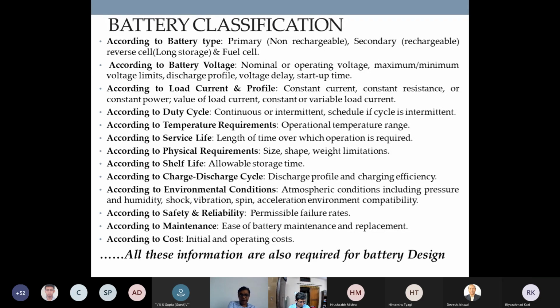Now there is another very important thing, which is temperature. What is the operating temperature range? For a battery like lead acid, the life capacity derating will be twice if I raise the temperature from say 25-degree nominal by 8 degrees. So what is the temperature - high temperature application, low temperature application? The electrolyte in a lead acid battery starts freezing at minus 16 degrees. There is IEC 60896 21 and 22 where we talk about testing of batteries at minus 16-degree temperature. The capacity at minus 16 degrees, or just above, may be 30-40% of nominal.